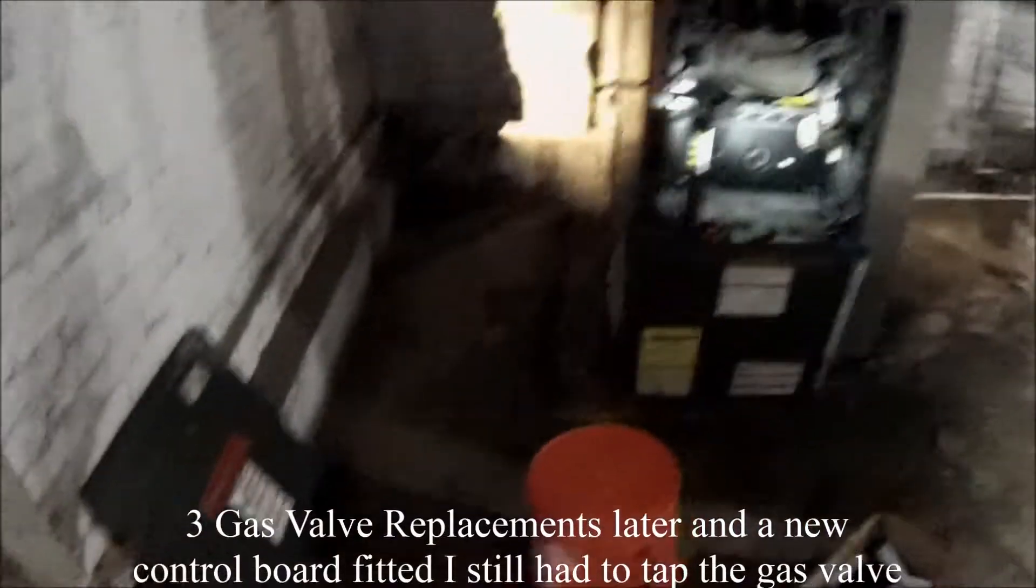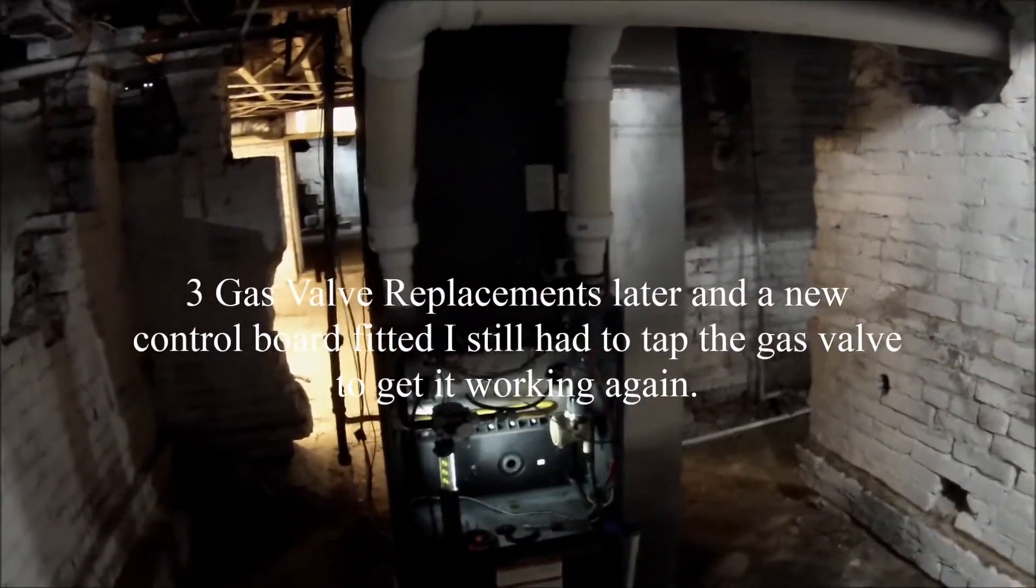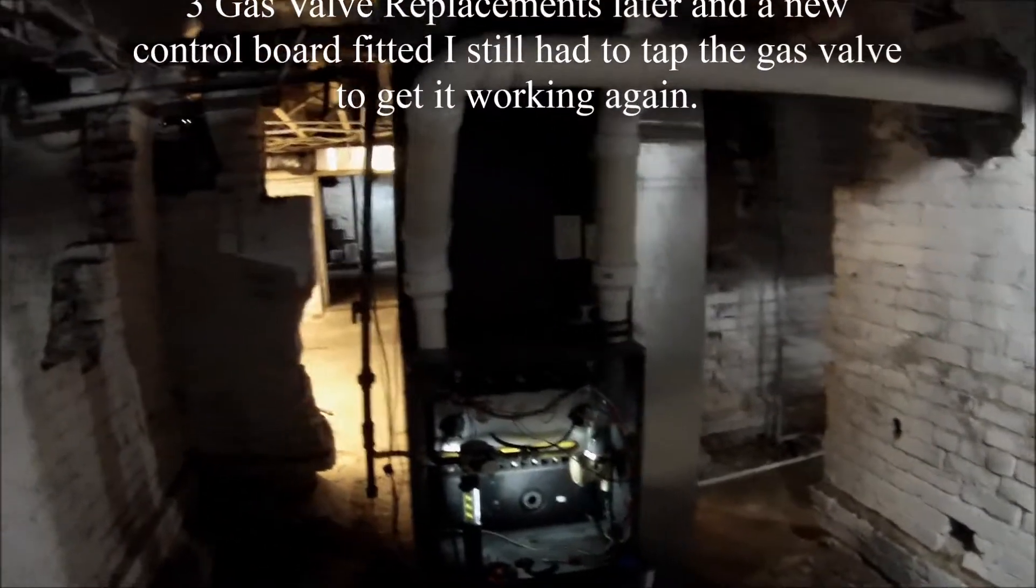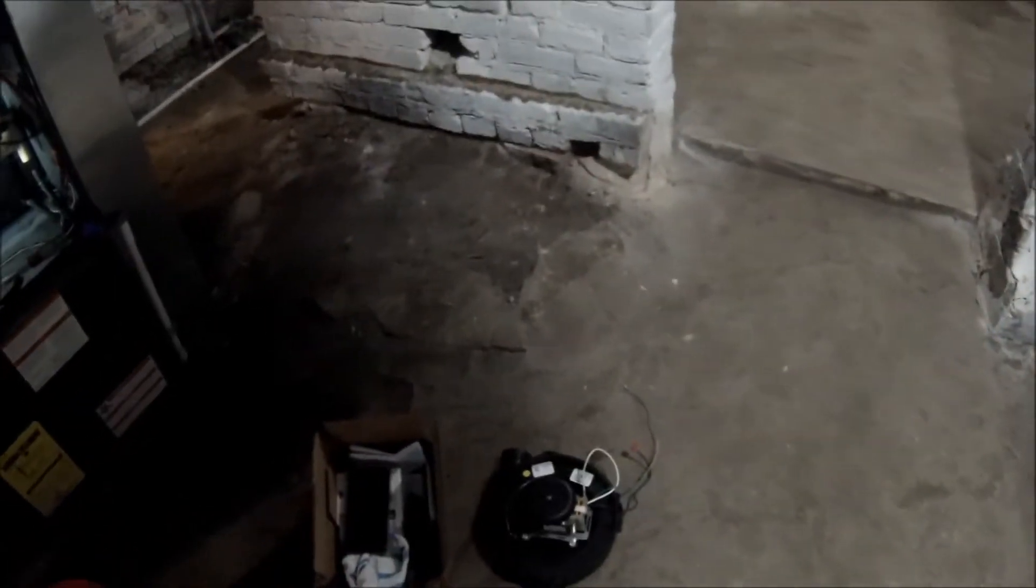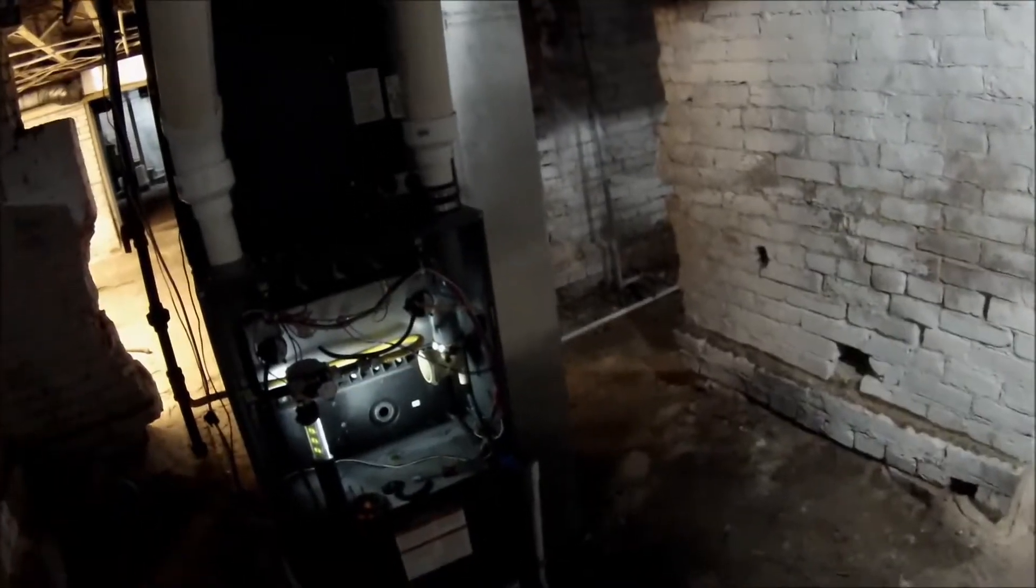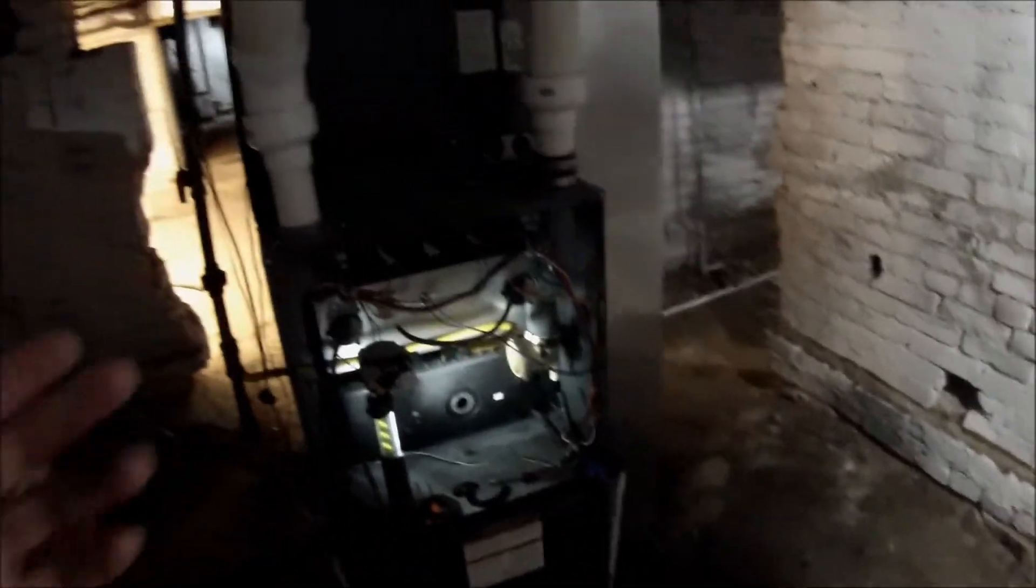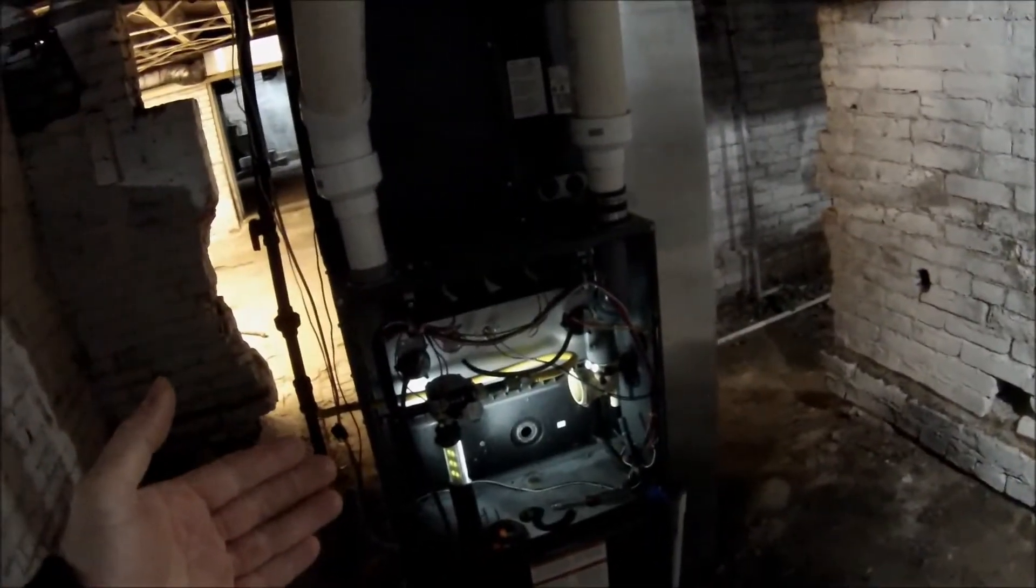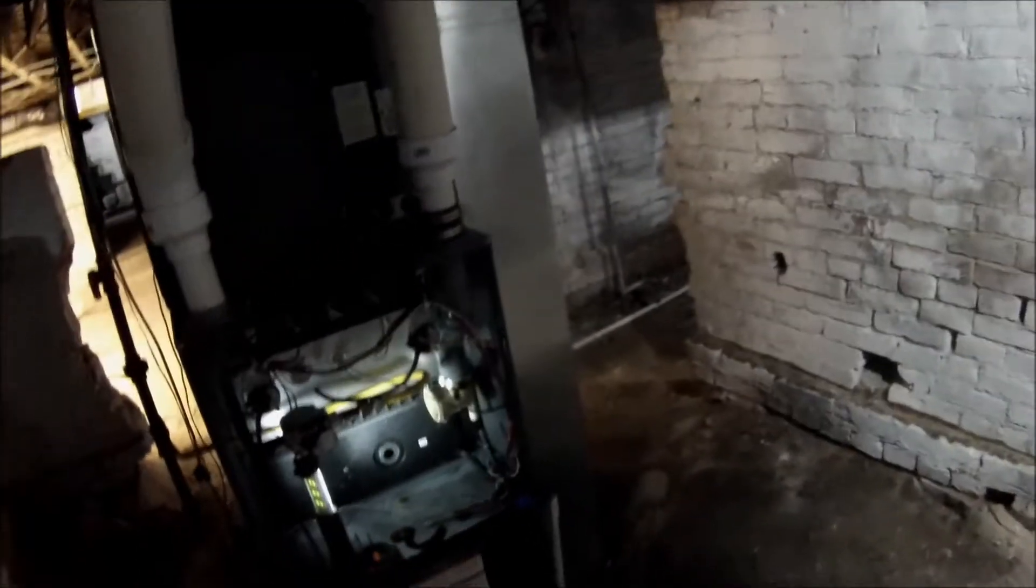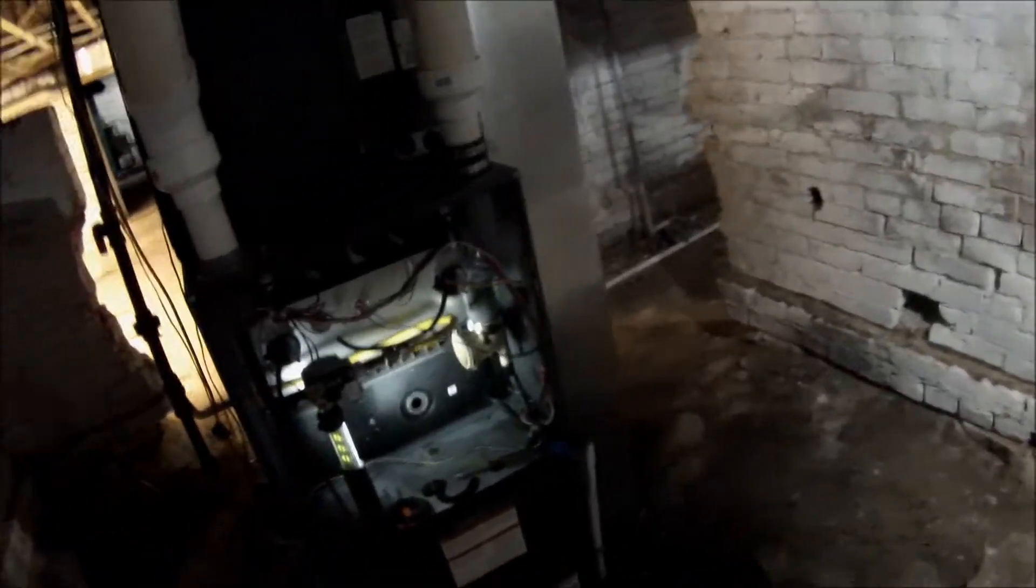Alright, so I got a Goodman HVAC furnace. And I've had some problems with it. I'm trying to explain as much as I can for myself and for YouTube. So my inducer motor, the old one, seized up. This thing wouldn't spin no more. So I went and bought a replacement, installed it. Then I started having problems with the heater not working. Like it would work and then not work. Work and not work. It would work sometimes and not. So I couldn't figure it out. I thought it was the gas valve. I kept getting, I bought three new gas valves. I kept putting them in there and it wasn't the problem. I went and I got a control board thinking I wasn't getting power to the gas valve. It wasn't the problem.